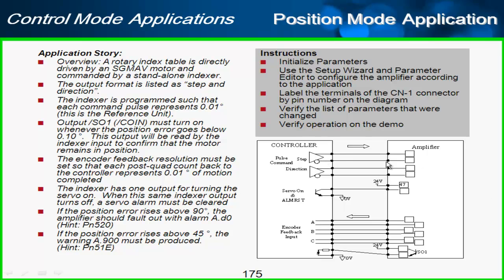So the controller is sending step and direction to the amplifier. And this indexer, this controller is programmed so that each command pulse represents 0.01 degrees. So one pulse here from the controller, the motor should go 0.01 degrees. By the way, that's called the reference unit when you are referring to the amplifier.